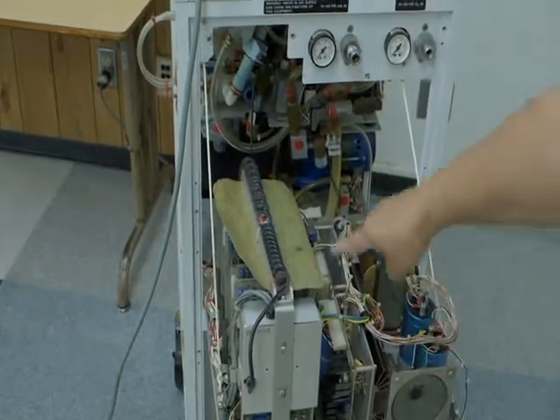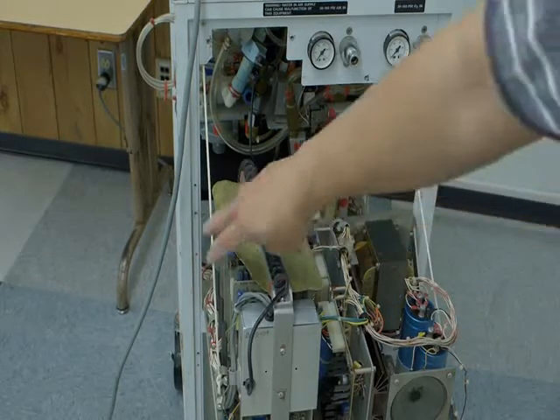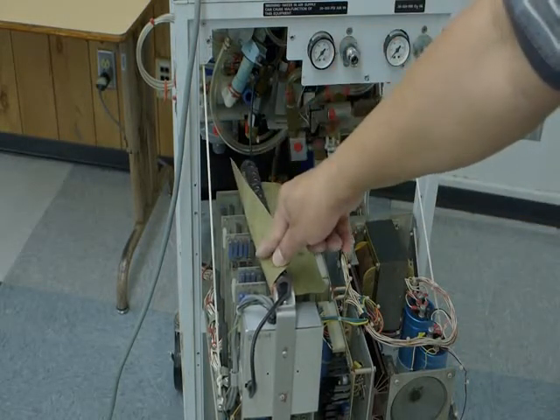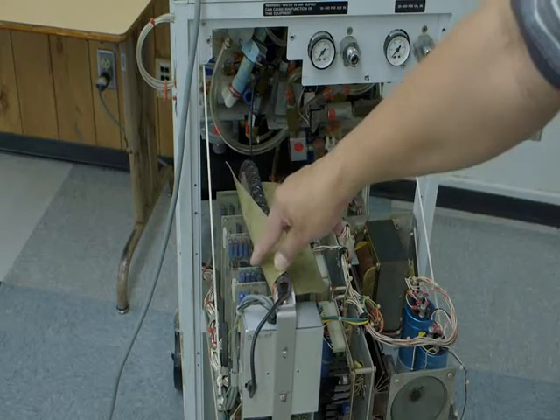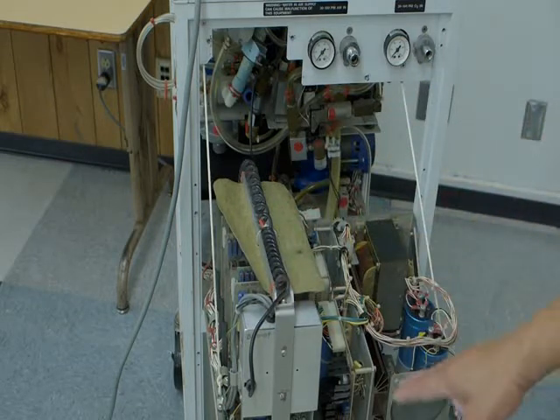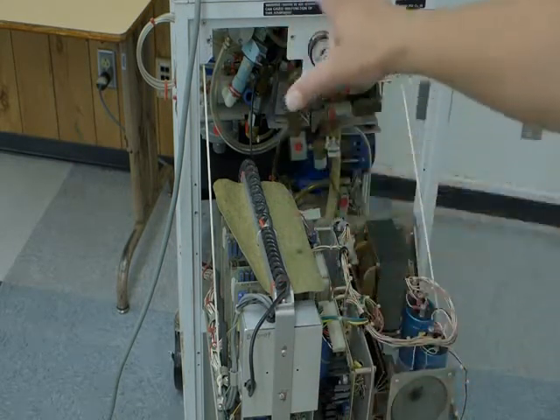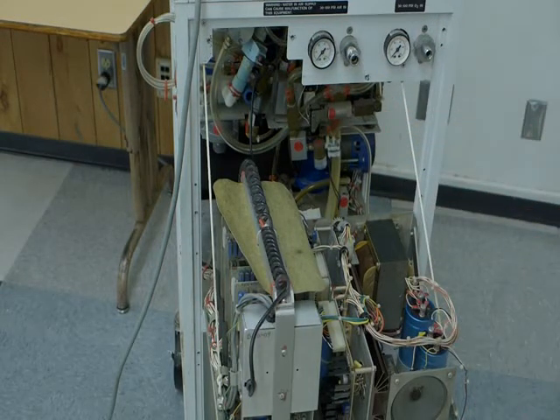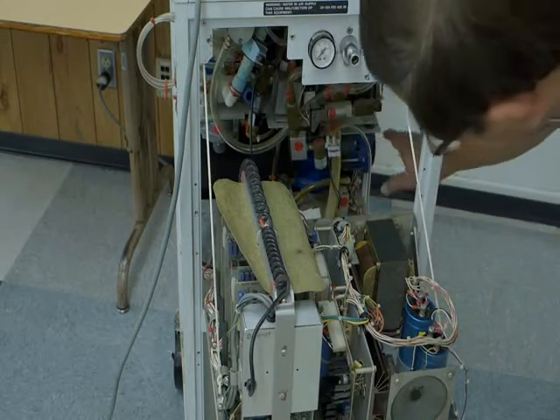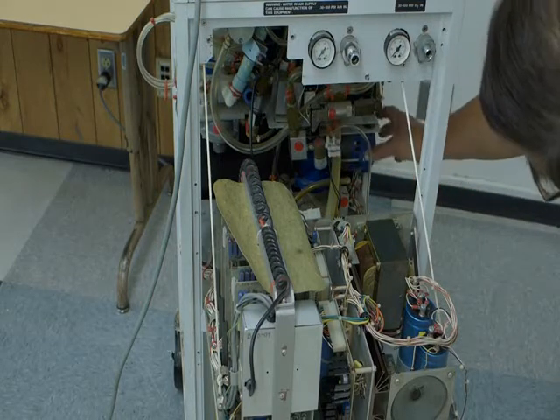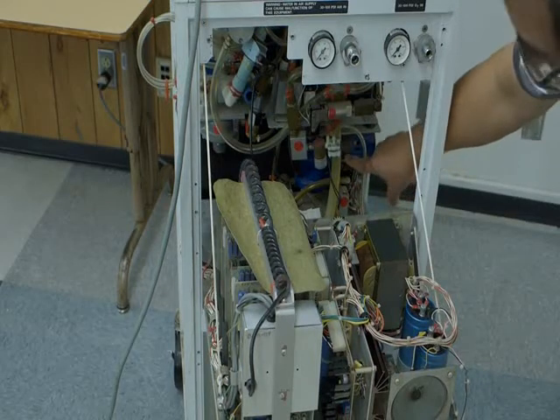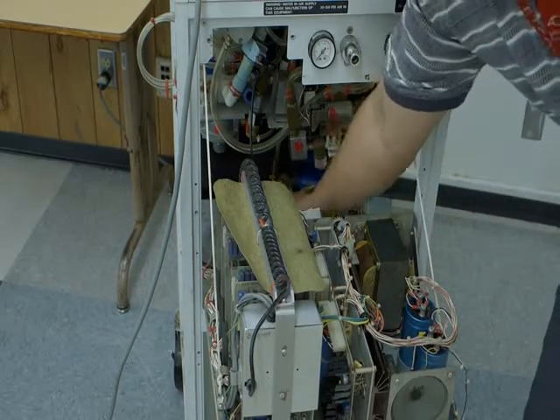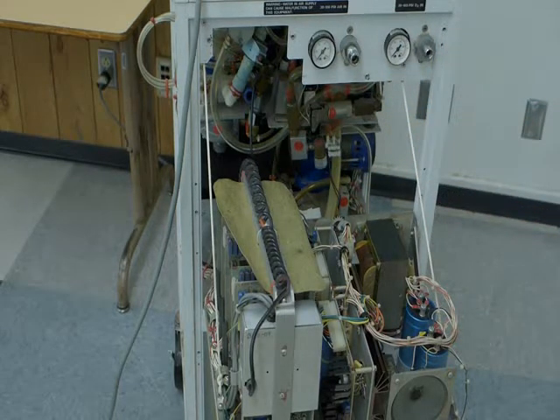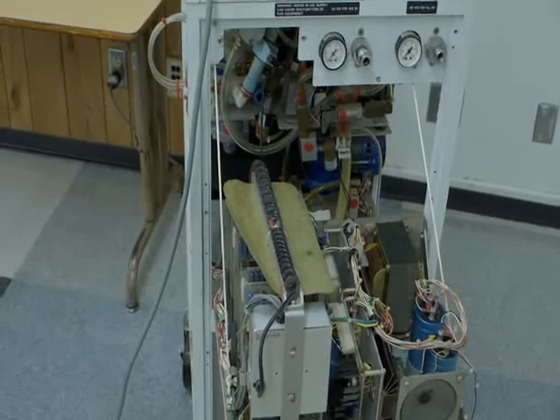This is the power supply system, and they have different circuits that control the alarms, with microprocessor control, that also supply the voltage to different components inside of the machine. You can see that inside they have a pneumatic system. They have pressure regulators. Down here they have a pressure switch. Also, they have some small pumps in here. It's for the nebulizer, and also underneath, down below the machine, is actually. Let me take that to show you.